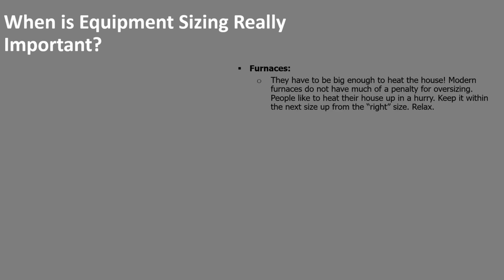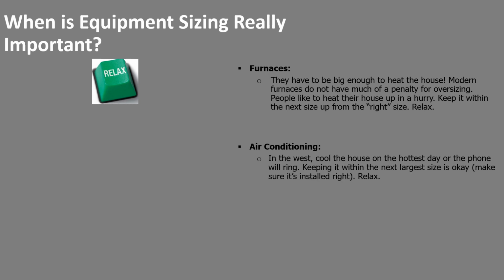When is equipment sizing really important? Furnaces, they have to be big enough to heat the house. New construction loads are usually below 20,000 BTUs. The smallest gas furnace we typically put in is around 40. So it's oversized by a factor of 2. I don't hear a lot of problems when this happens. So I think, relax.